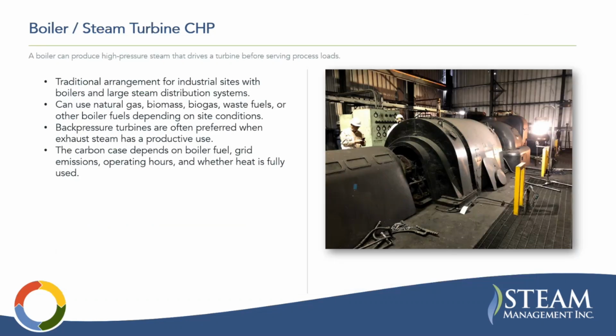Probably the most traditional arrangement for industrial sites is a boiler and steam turbine combo. This is what I think of when somebody mentions cogeneration. It's the first thing I think of anyway. Like I said, you can use basically all the common fuels to generate the high pressure steam. Then you're going to send that through a back pressure turbine. You may have a combination of back pressure turbines for different lower pressure steam systems. If it's a big complicated facility, you may still have PRVs on the side.